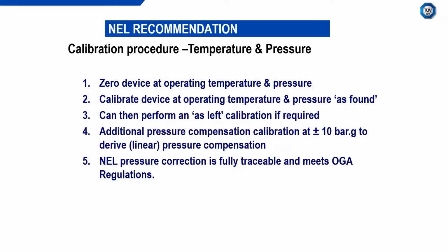So we recommend you zero the device at operating temperature and pressure. Calibrate the device at this condition as found. You can then perform an as-left calibration as required. Remember, that doesn't have an effect on the pressure effect.